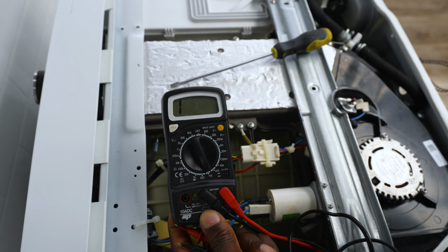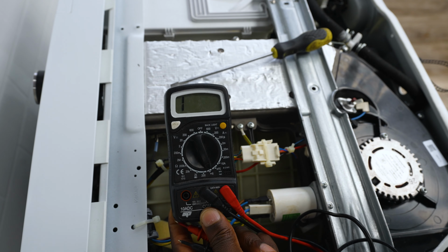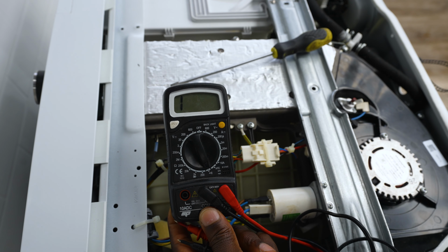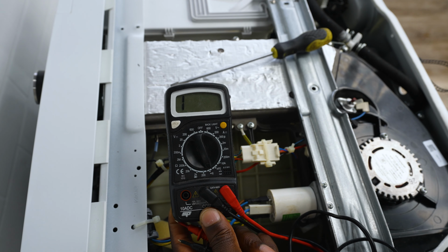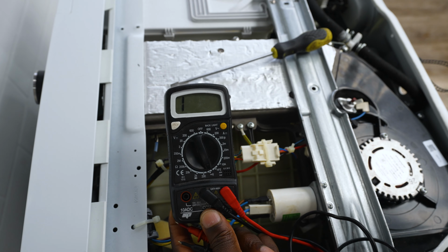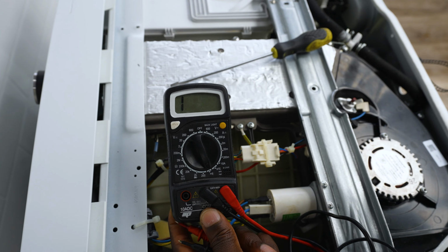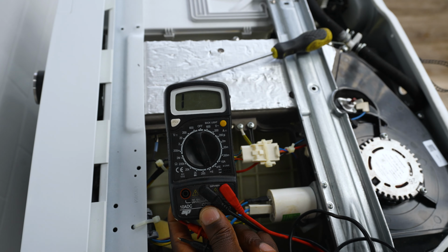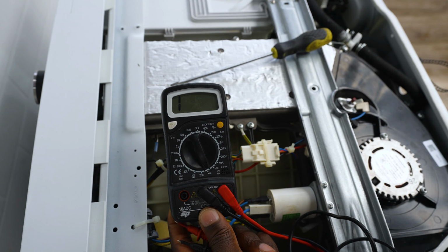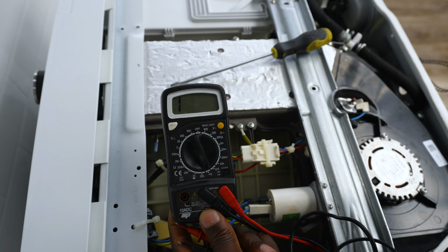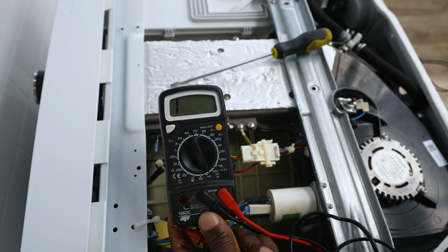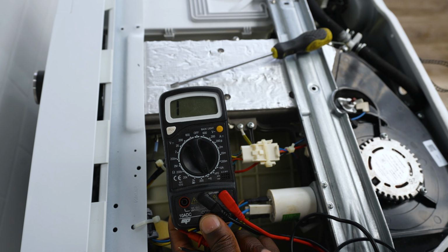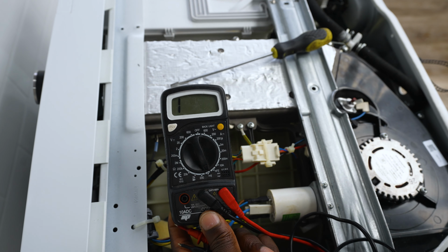Your heating works by that resistance. When you're getting resistance, that's how you heat up the element. The heating is electrons moving along your heating element, that coil of wire, and that's what creates the resistance. So if there's a break in the wire inside your heater, there's no more resistance — it's more like any other wire with a break in it. So we need to test to make sure it's got some resistance in it.